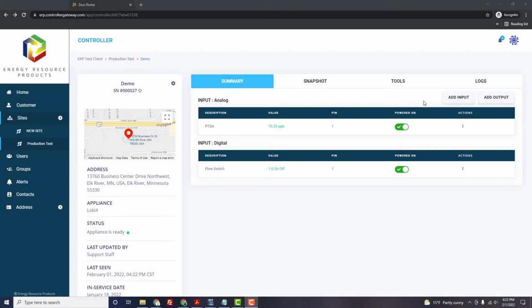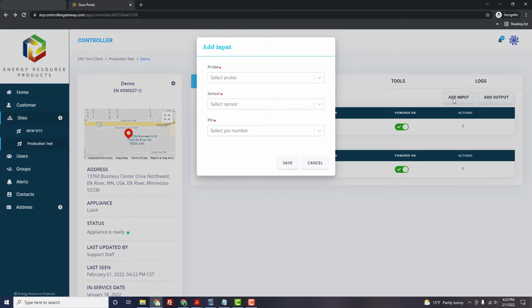From the summary page, select Add Input. Also, when first setting up your Modbus probes, it is important that only one probe be physically attached to the controller. When you complete the programming of the first probe, you can then physically connect the next probe and repeat the process. This is necessary so the controller can identify one probe at a time at startup.